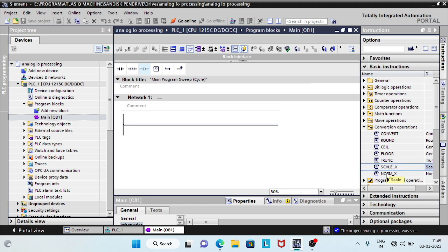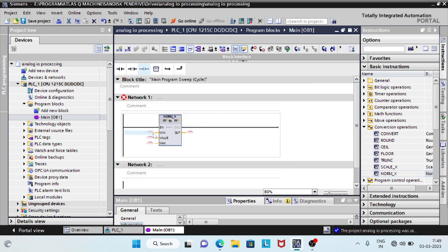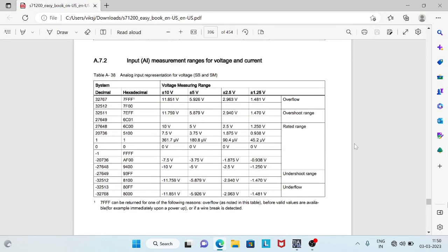The NORM_X function normalizes the value inside the range specified by the min and max values. For the normal range, the minimum value is 0 and the maximum value is 27,648 for 0 to 10 volts.